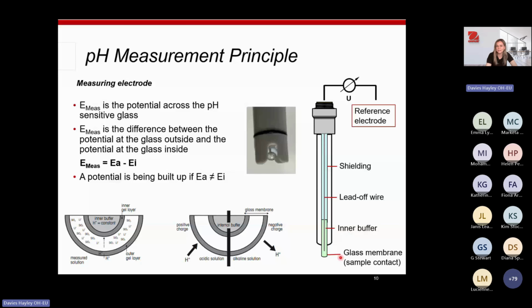So the glass membrane is kind of the most important thing on the electrode. We mentioned that the special type of glass reacts with an aqueous solution, and it forms a gel layer. So you will form a gel layer on both the inside and on the outside of the glass. And that gel layer acts like a sponge for hydrogen ions, or H+ ions.